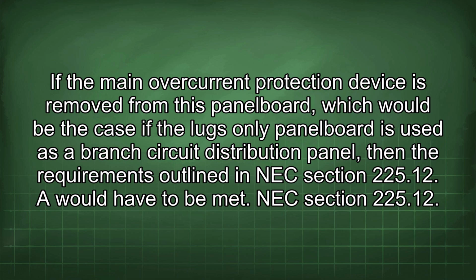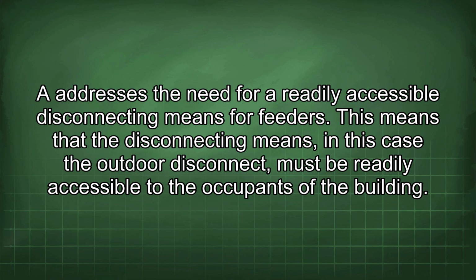If the main overcurrent protection device is removed from this panel board, which would be the case if the lugs-only panel board is used as a branch circuit distribution panel, then the requirements outlined in NEC section 225.12(A) would have to be met. NEC section 225.12(A) addresses the need for a readily accessible disconnecting means for feeders.